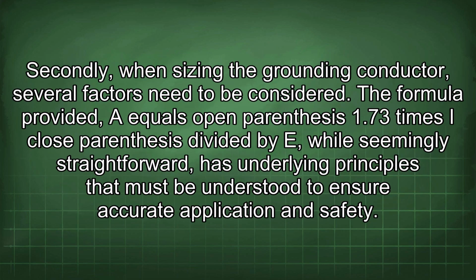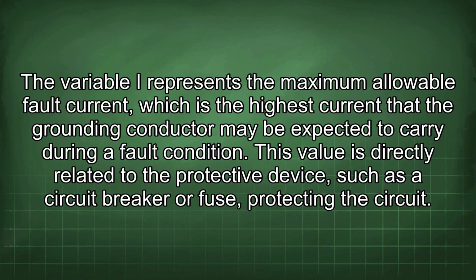Secondly, when sizing the grounding conductor, several factors need to be considered. The formula provided, A equals open parenthesis 1.73 times I close parenthesis divided by E, while seemingly straightforward, has underlying principles that must be understood to ensure accurate application and safety. The variable I represents the maximum allowable fault current, which is the highest current that the grounding conductor may be expected to carry during a fault condition.